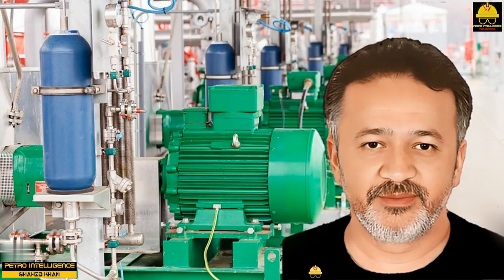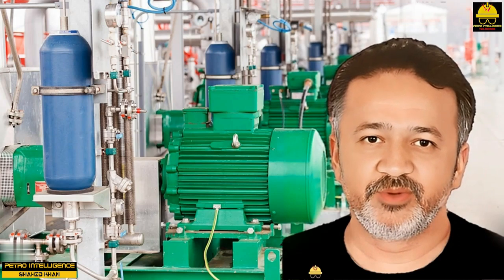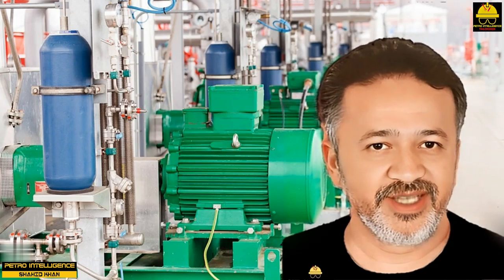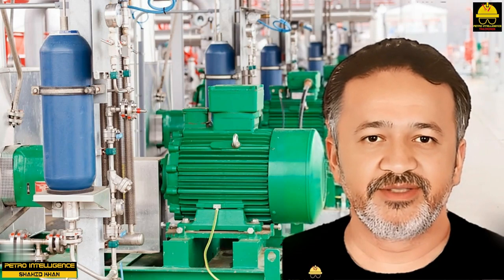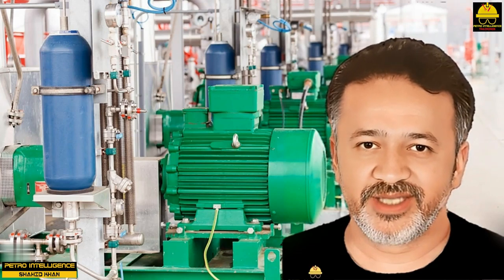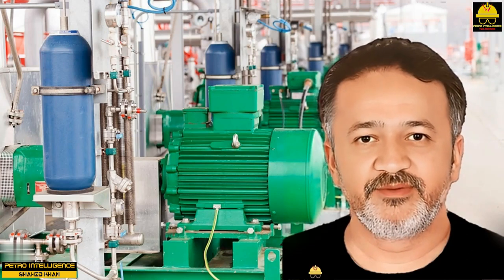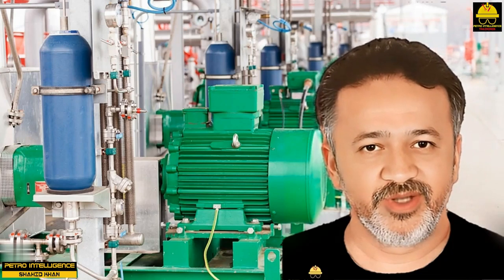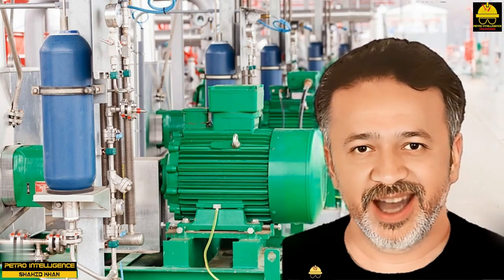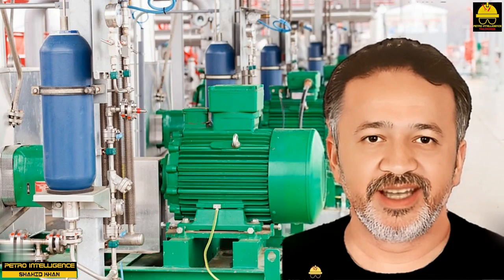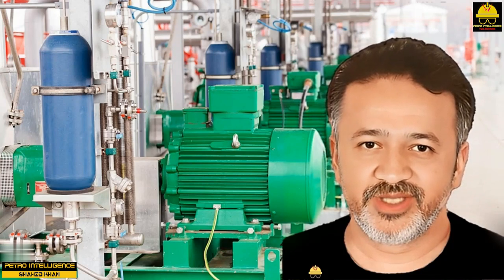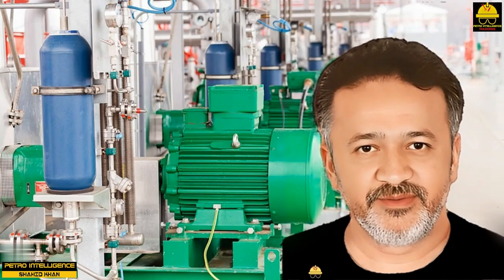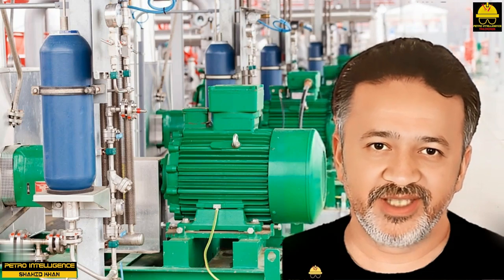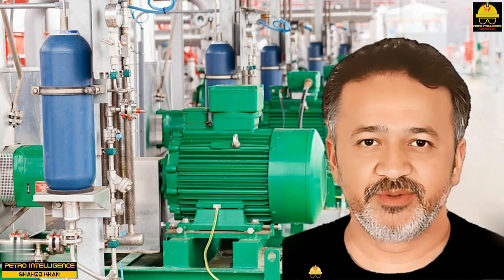Rotor and stator. The rotational speed of the rotor and the total volume of the cavities determine PC pump flow rate. The rubbing velocity determines rotor and stator life. If the space between the rotor and stator is small, a high degree of rubbing velocity is created. Rubbing velocity is a major factor in the life of the stator. The stator can be replaced after it is worn out.